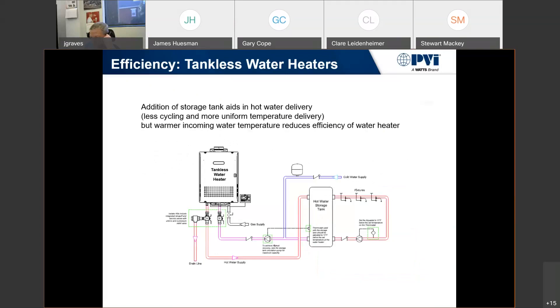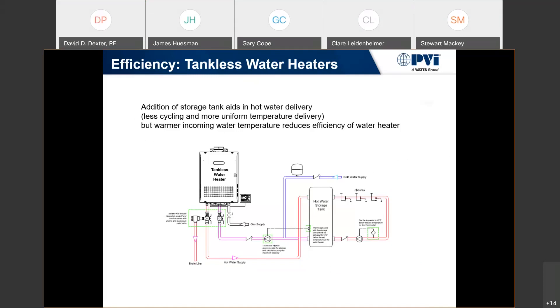For most instantaneous appliances in a commercial design, they want to minimize short cycling. If there's minimal flow going into the system, we also have a return loop coming back — these things fire on flow, so if they see flow, they fire. In order to mitigate that short cycling, they install storage. This is a very common design where a tankless water heater with storage is implemented.